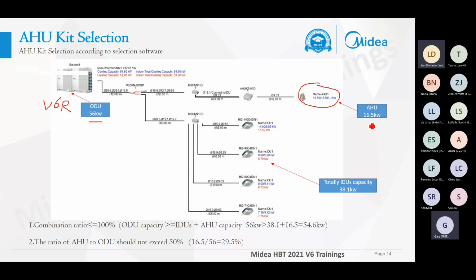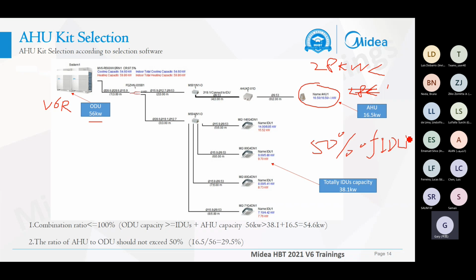The capacity is 16.5 kilowatt, and this AHU kit capacity is less than 28 kilowatt. Sorry, is less than 28 kilowatt. This rule is correct. And totally the indoor unit capacity is about 38 kilowatt, and the AHU kit is less than 50% of the total indoor unit capacity. This rule is correct. So this section is correct.